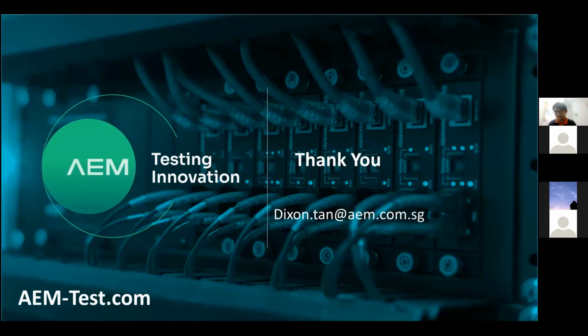Yes. One of the things PoE devices has is what we call a handshake. When the PoE source recognizes the device, it opens up the channel for power to pump through - first for safety reasons, and second to ensure you don't generate power unnecessarily if there's no device connected. So to ensure the power continues running through the cable, we provide load test equipment to simulate the device, to open up the channel for the PSE, or power source equipment, letting it know there is a device connected so it needs to continue supplying power.